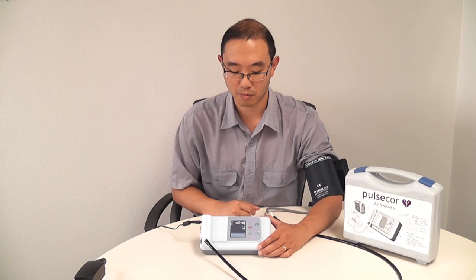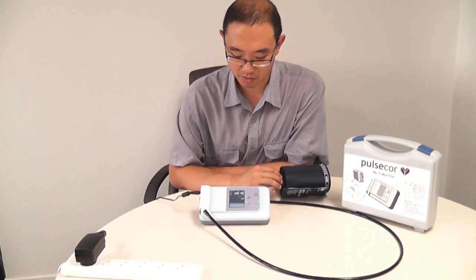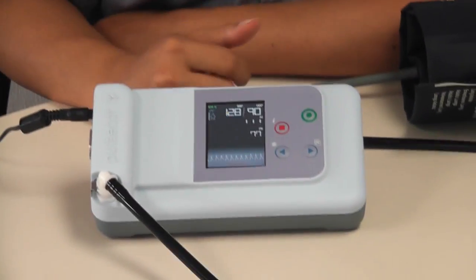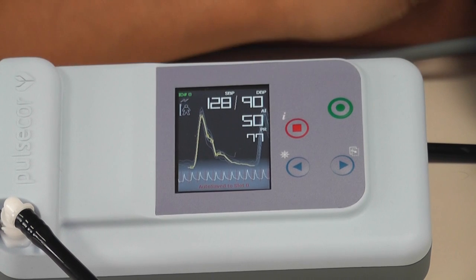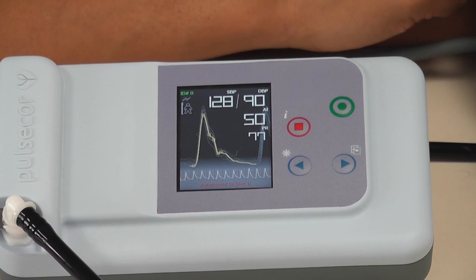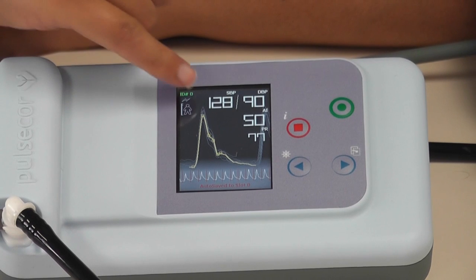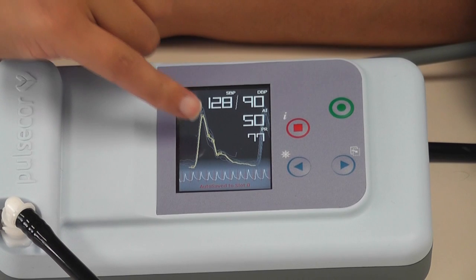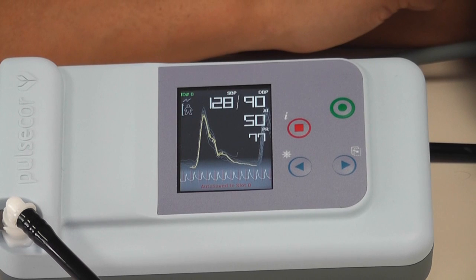The measurement has now completed. I can take this cuff off. It's measured my blood pressure at 128 over 90. My pulse rate is 77. You can see down here the rhythm strip, which gives each individual heartbeat. It also calculates an average waveform, which is the shape in yellow. It calculates an augmentation index of 50% — that's a peripheral augmentation index. You can see the incident wave here, which is the wave directly into my arm, and also the reflection wave, which is that little indentation buried in the side of the incident wave.